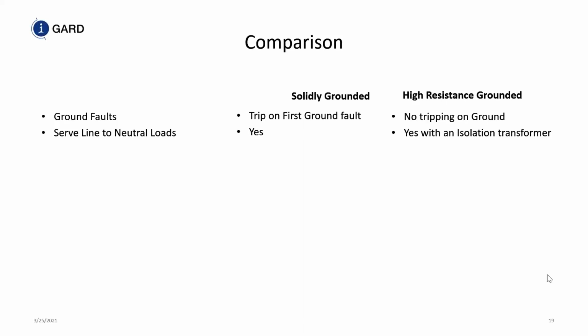Here's where we differ now between Canada and the US. In Canada, you're allowed to have phase to neutral loads on a resistance grounded system. However, you must trip when you have the first fault. So it really doesn't benefit you in having a distributed neutral on a resistance grounded system. Instead, you could service that 277 or 347 volt lighting with an isolation transformer. So if you put in a 112 kVA transformer from 480 to 480/277, or 600 to 600/347, now you can service the lighting load.